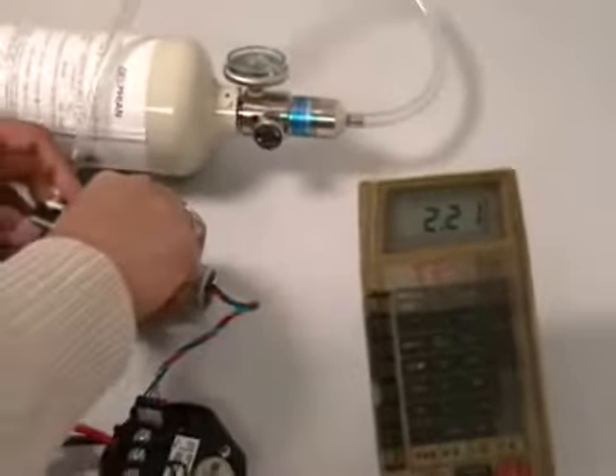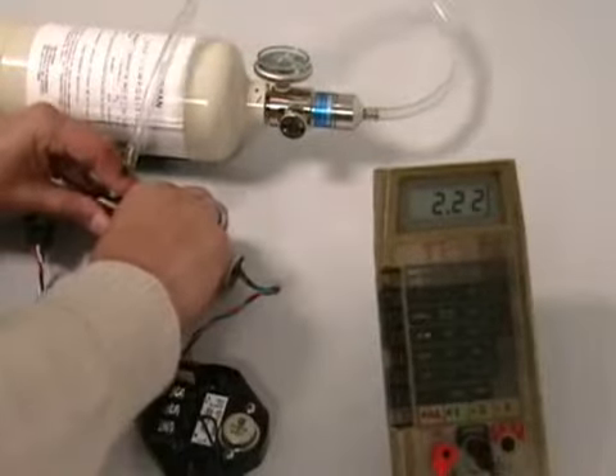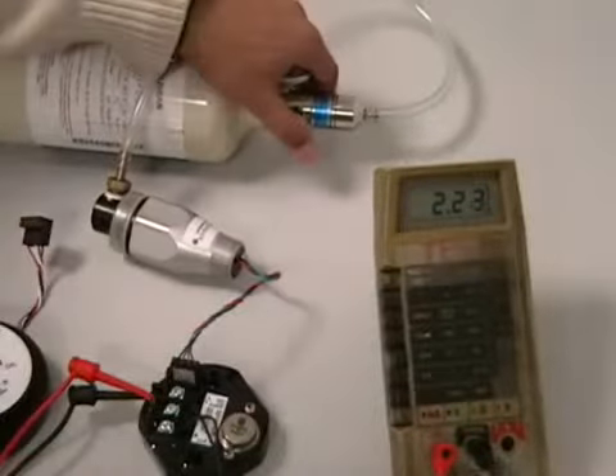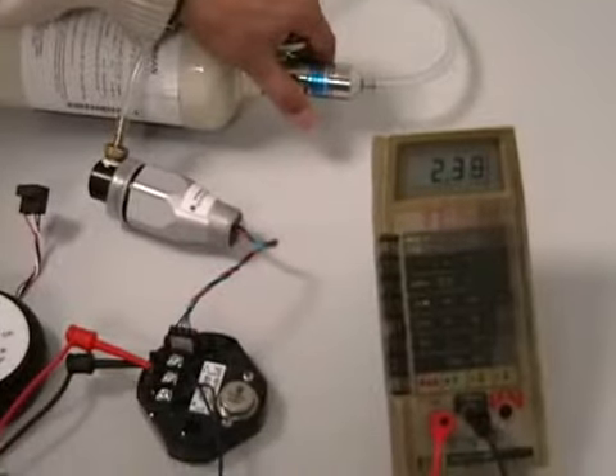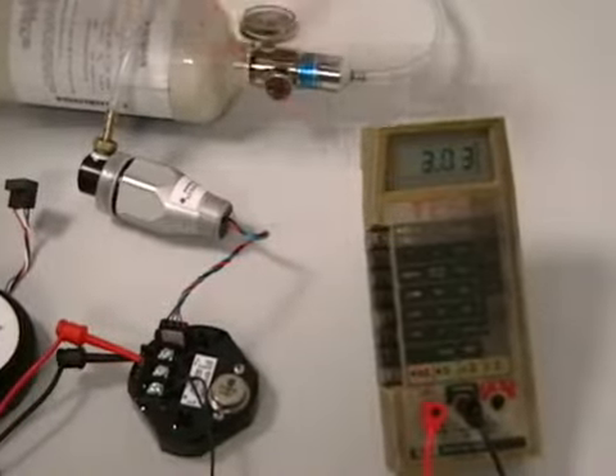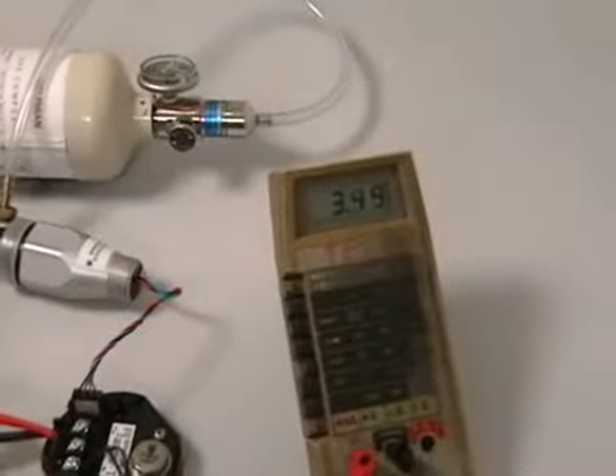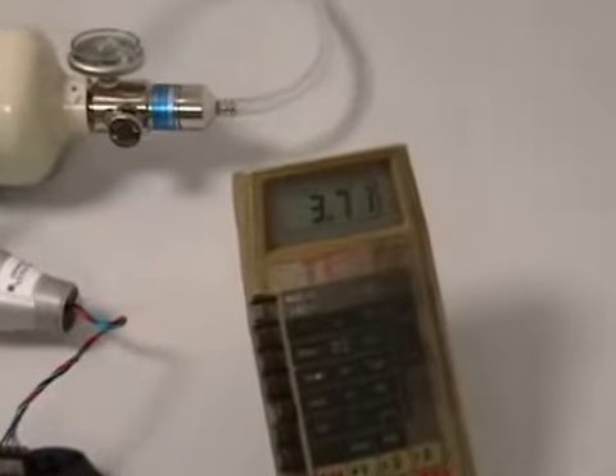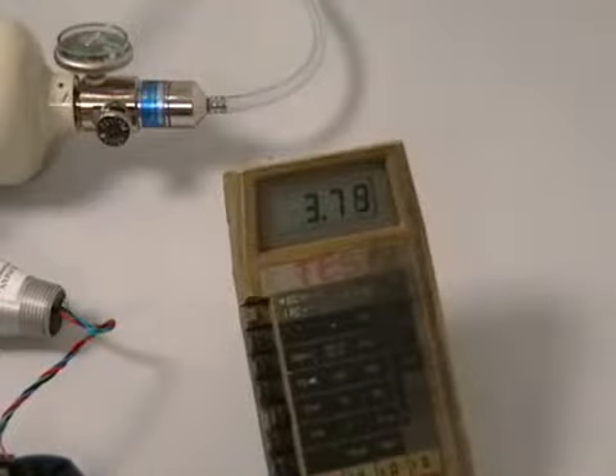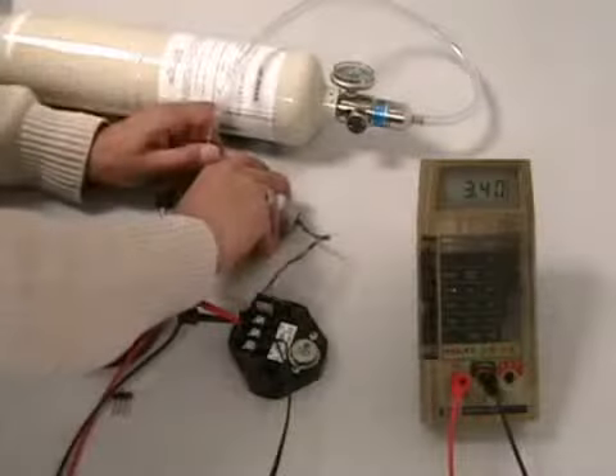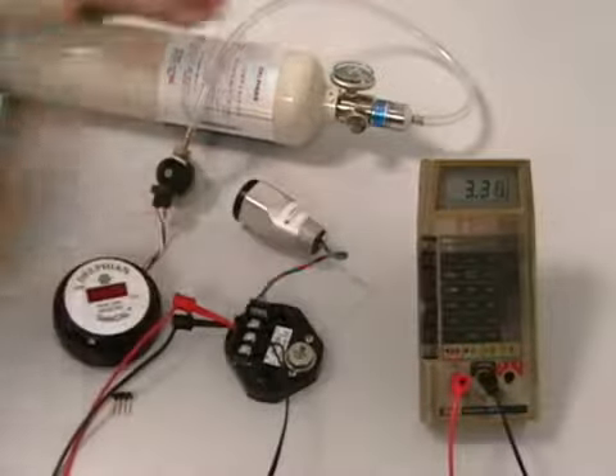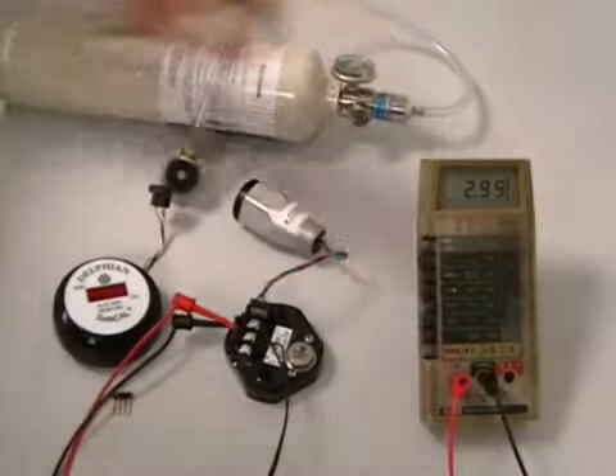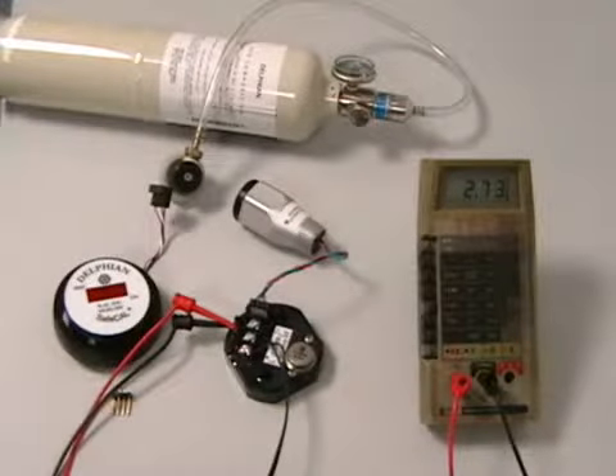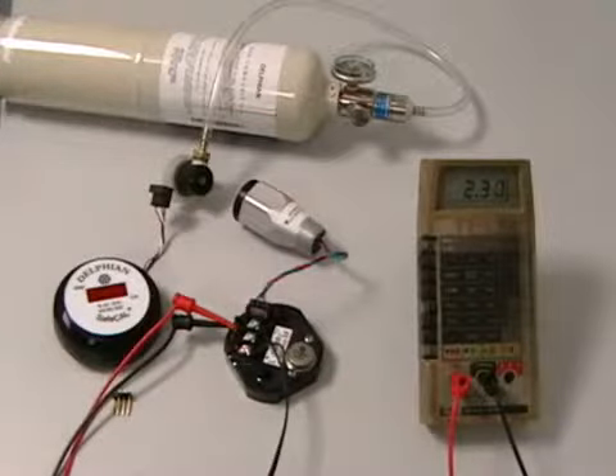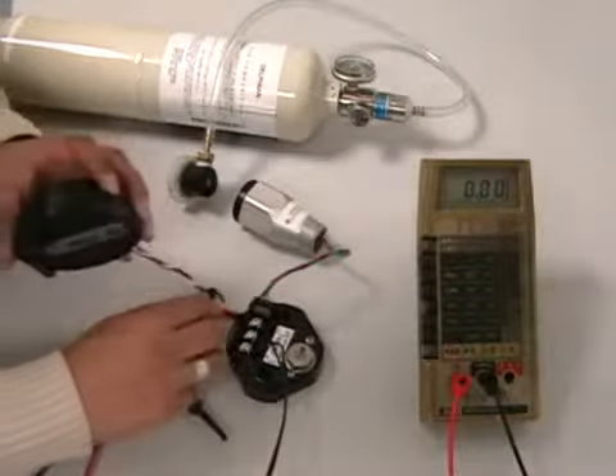Now you can snap on the sensor gas connector and supply a 50% LEL gas in air mixture to the sensor. A change in span from its zero reading, in this example 2.21 milliamps, to its span reading is called the delta change and should be approximately 3 to 3.5 milliamps on a new sensor to as little as 0.5 on an aged or poisoned sensor. In this example, our span is 3.8, giving a delta span of approximately 1.6 milliamps. This is a perfectly good working sensor transmitter assembly, indicating a sensor through about half its life.